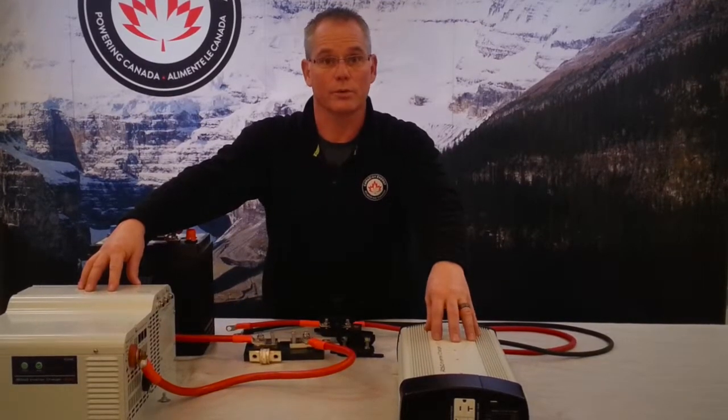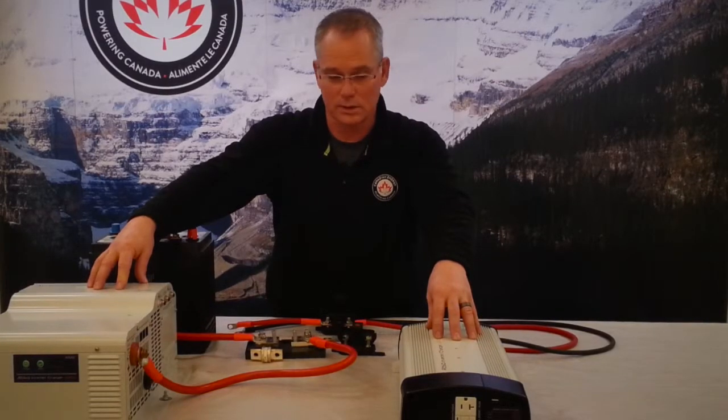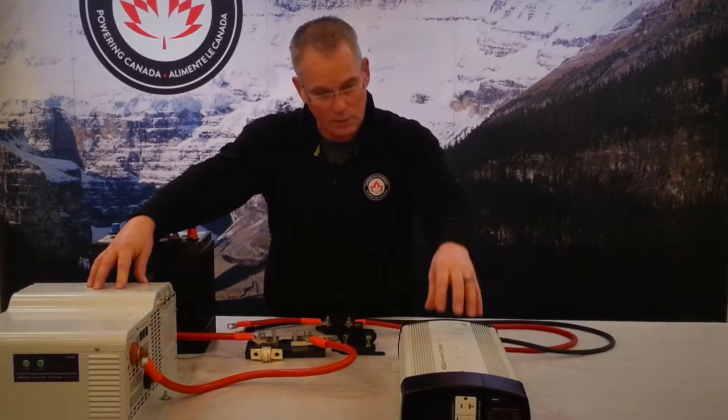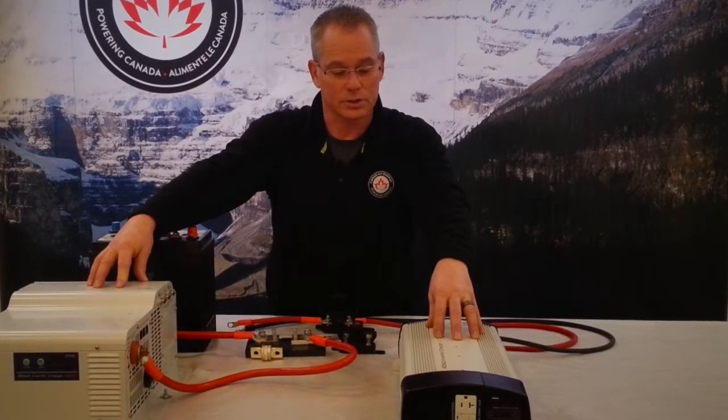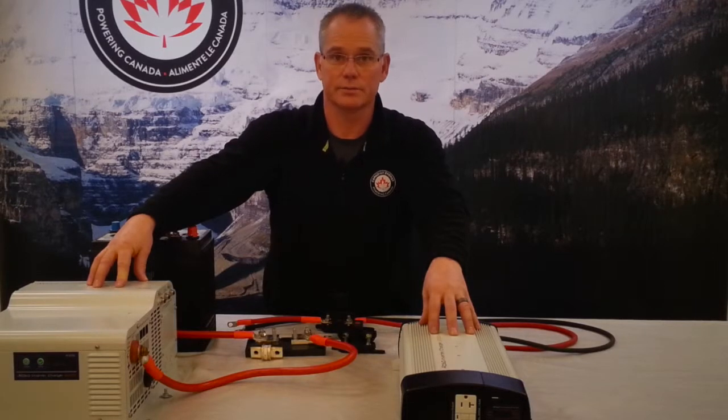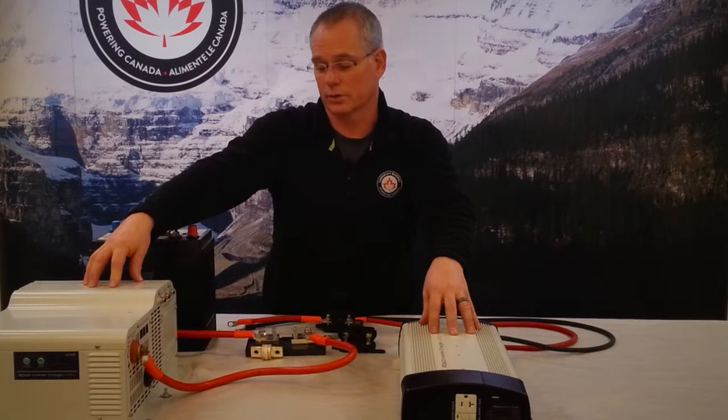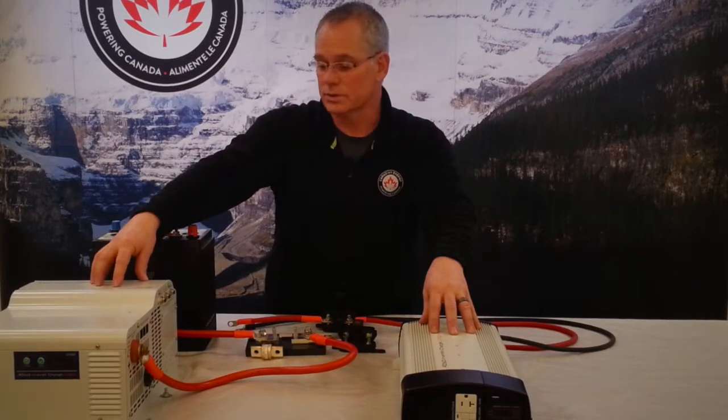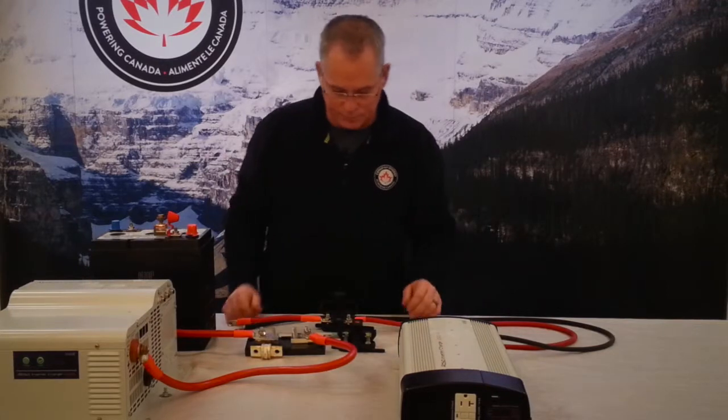So this 2000 watt will put out 4000 watts. The 3000 watt will put out 6000 watts. The difference being is the high frequency or the electronic based inverter charger will only surge for milliseconds, a very short period of time. The low frequency transformer based inverter charger will surge two times capacity for five seconds. That brings us to the fusing.